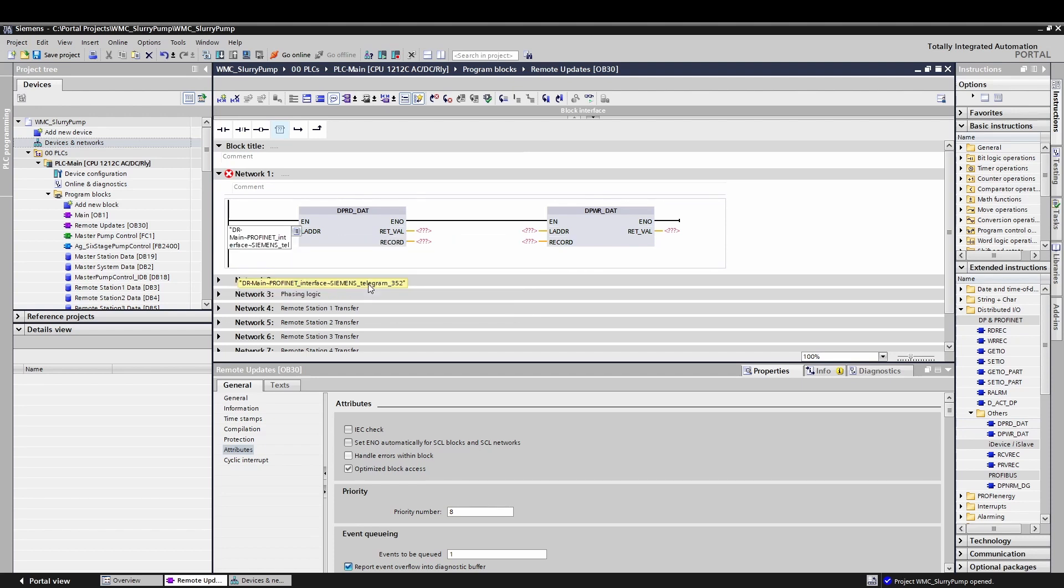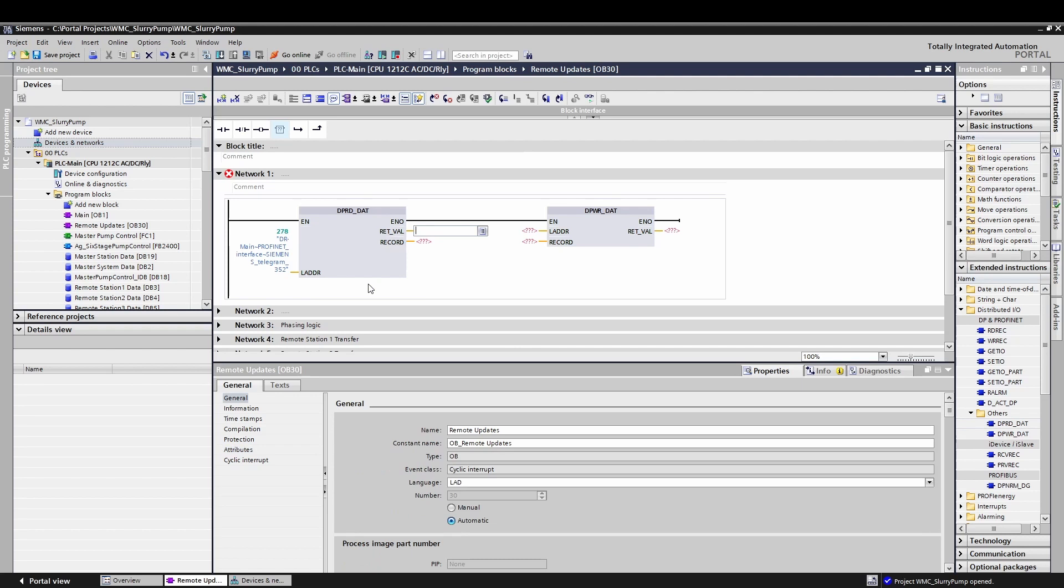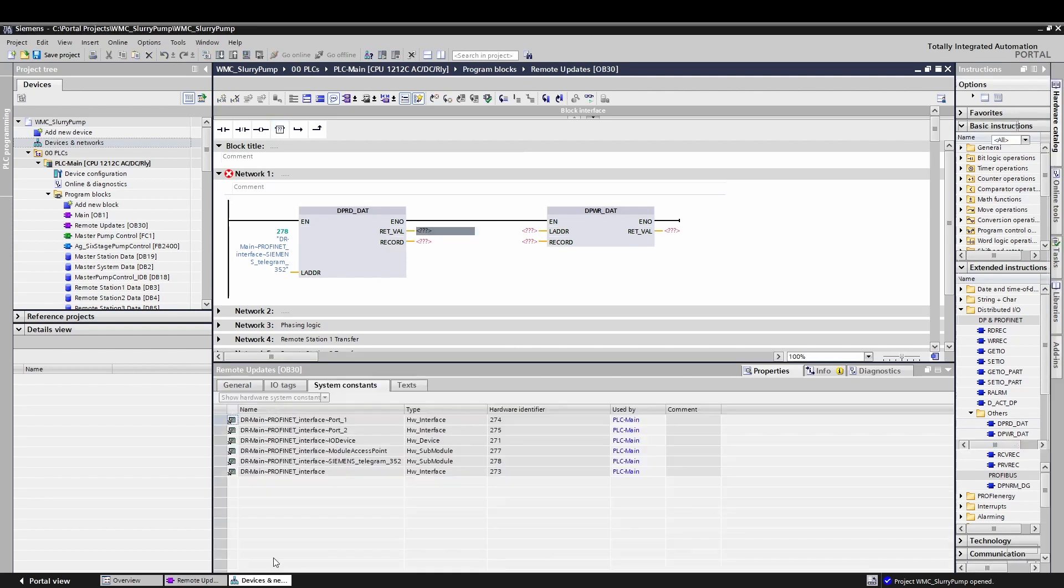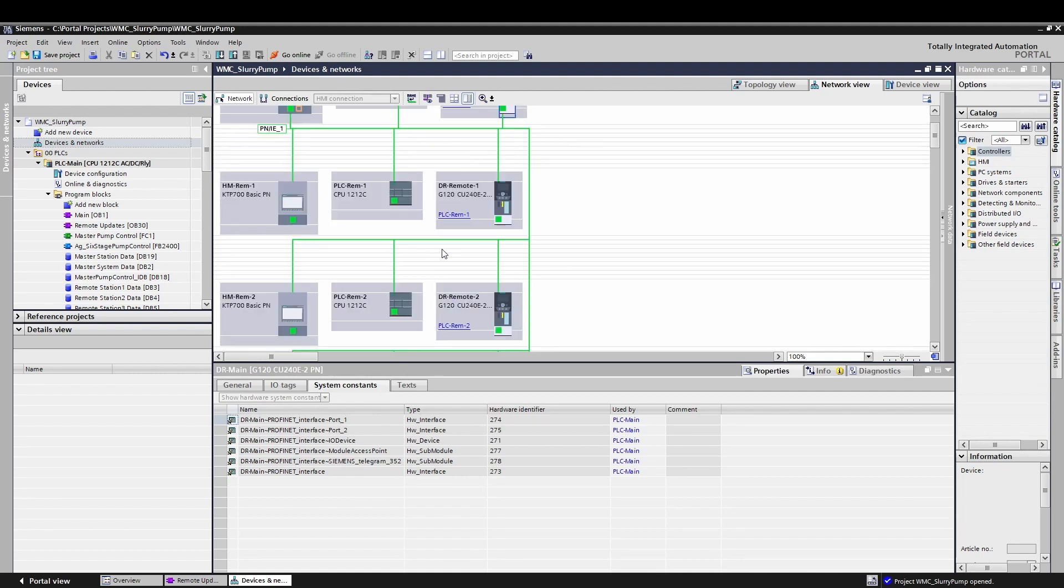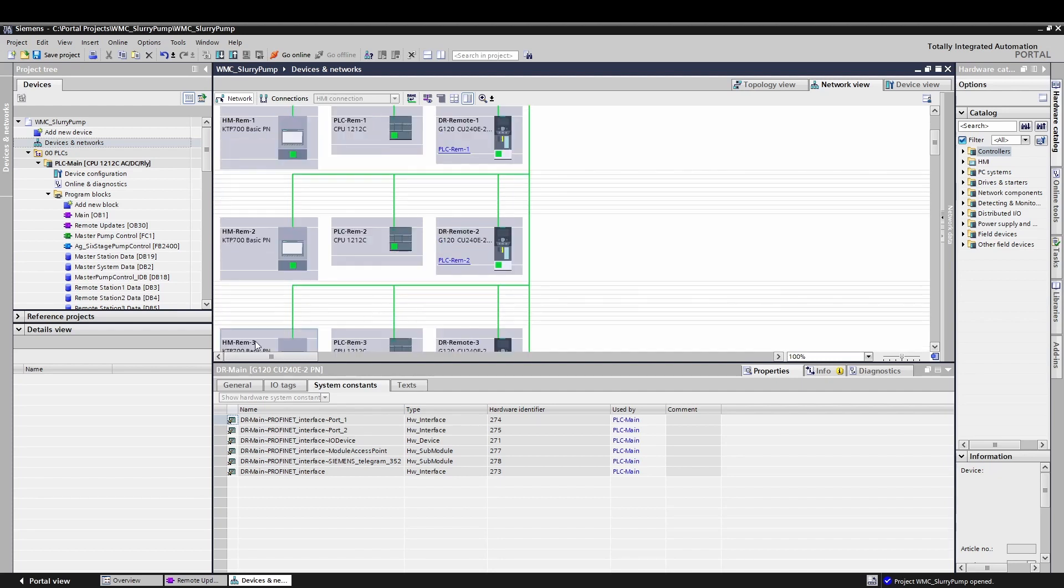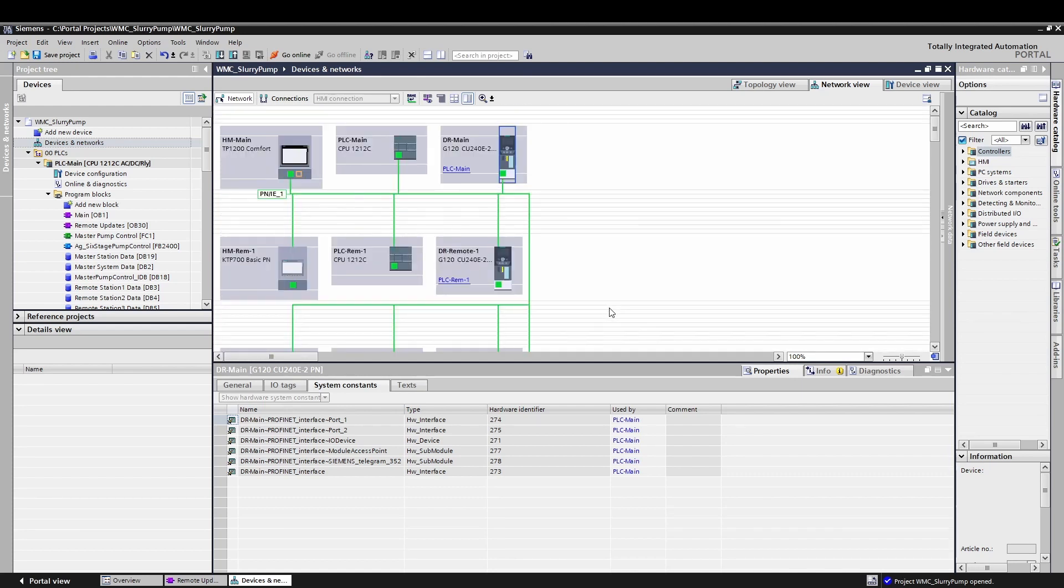A better way is you can start typing the name of the device and find the appropriate system constant tag. If you don't take the time when you first set up your system to name your devices in a certain way, this can cause problems. That is why in most of my real projects, you will see the same naming scheme. Of course, I will mess up every now and then and not follow the same scheme if I'm in a hurry. But always, always, always name every single device in the network view something other than default. It will save you ages of time and headaches.